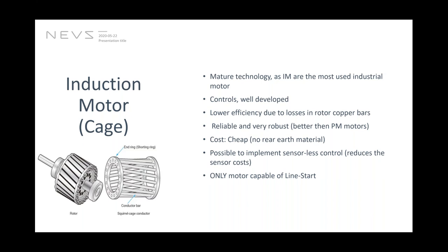So what's the maturity level of the induction motor? This is the most used industrial motor, and the technology is very, very mature. Even the controls are well developed. It has slightly lower efficiency compared to permanent magnet motors and synchronous reluctance motors, because there are quite a bit of losses in the rotor bars, and especially with VFD application, those losses tend to increase. These machines are very reliable and robust compared to permanent magnet, which I will explain later on. And given the well-developed manufacturing process and the maturity of the technology, these motors are really cheap, and they also do not use any rare earth metal, which helps in keeping the cost down.